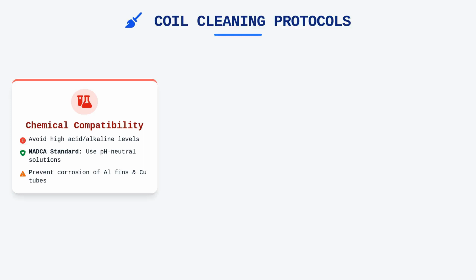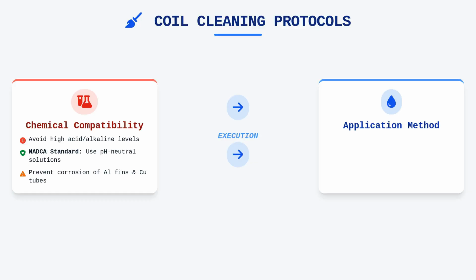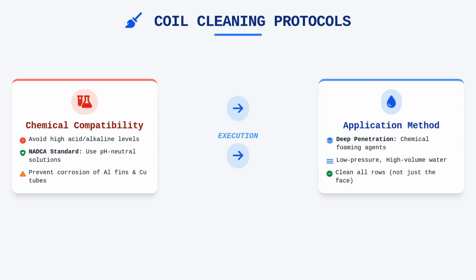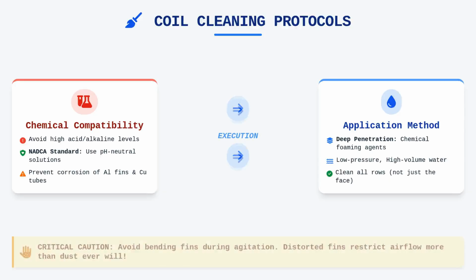For thick, multi-row coil banks, simply spraying the face of the coil is almost never sufficient to reach the rear rows where organic material thrives. You must often employ low-pressure, high-volume water application combined with specialized tools, such as chemical foaming agents that can penetrate the full depth of the fin stack. During mechanical agitation, one must exercise extreme caution to avoid bending the fins, as distorted fins restrict airflow far more than a light coating of dust ever would.